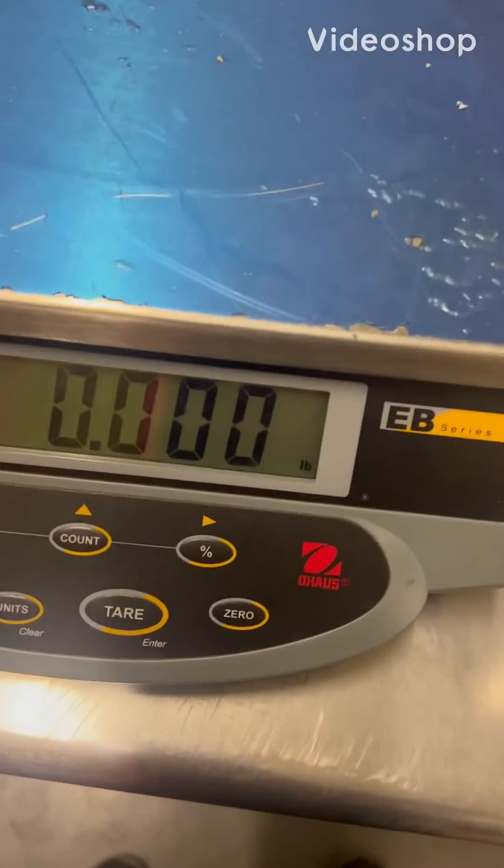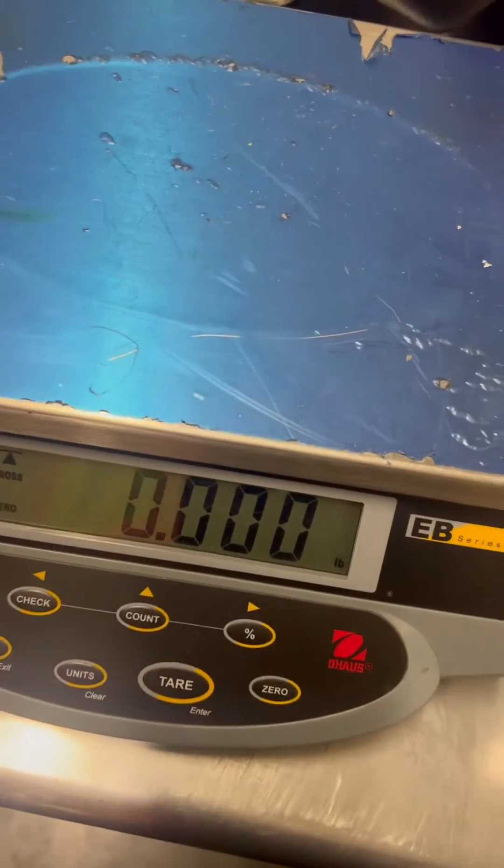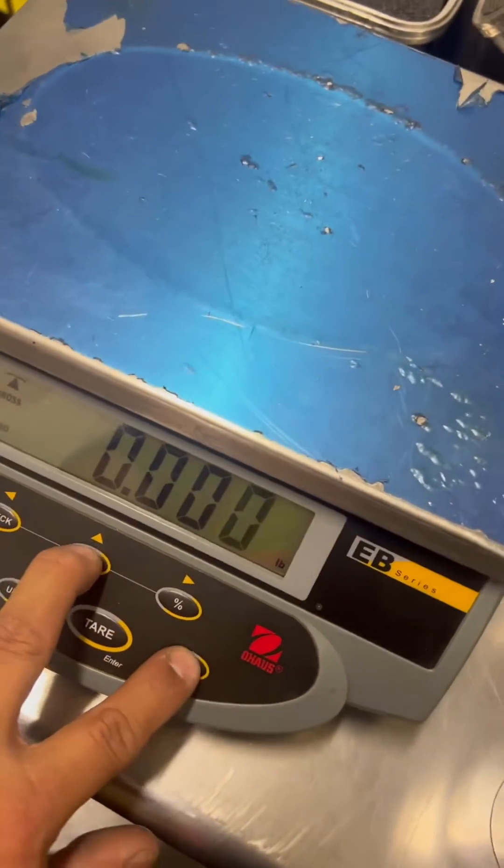This is a calibration adjustment of an old Ohaus EB series scale. Basically, you would hold down the count and the zero key at the same time.